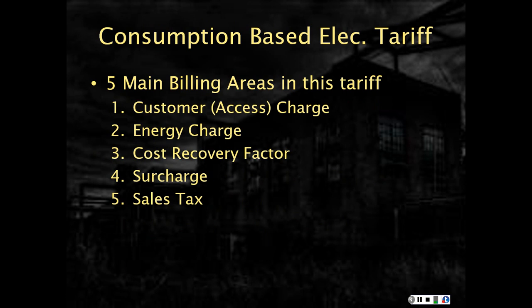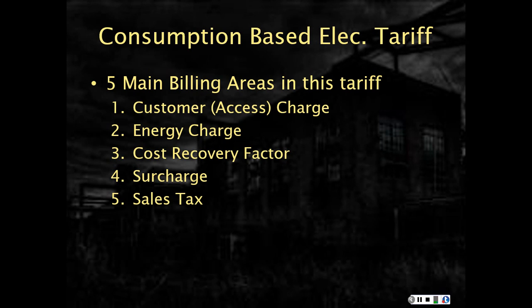Now we're going to look at a consumption-based electrical tariff. There are five main billing areas in this tariff. The first is the customer or access charge. The second is an energy charge — as you remember, energy is equivalent to KWH, electrical usage and consumption. There's also a cost recovery factor, followed by surcharges, and then possibly state sales tax.